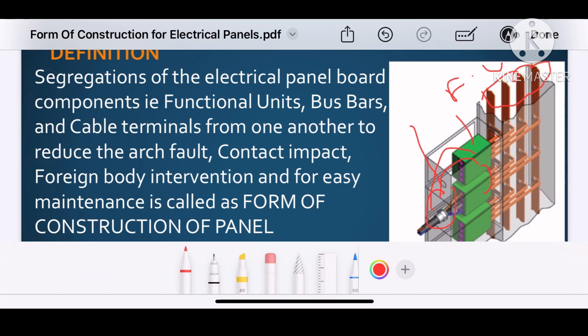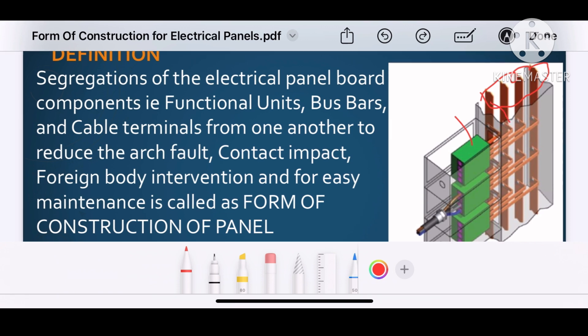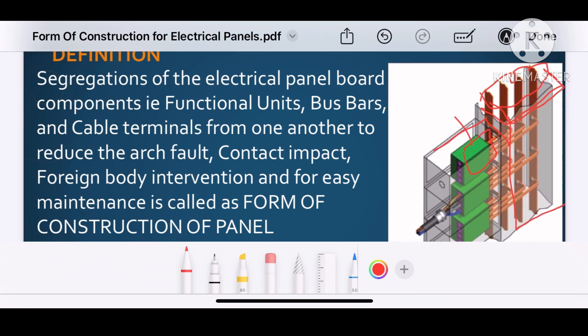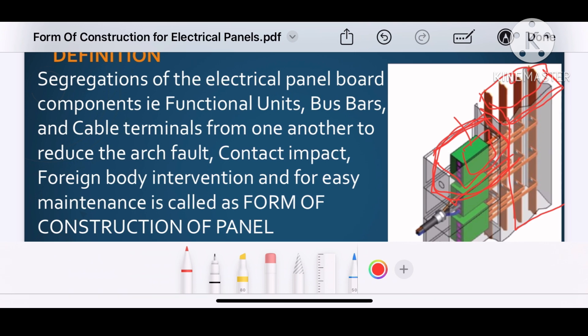As a whole, the degree of separation between the bus bar to functional unit, functional unit to functional unit, and the functional unit to the cable termination is called the form of construction for the electrical panel. In this example, you can see that the bus bar is separated through a film from the functional unit, and the functional unit itself is separated from other functional units by a compartment, so there is a degree of protection.